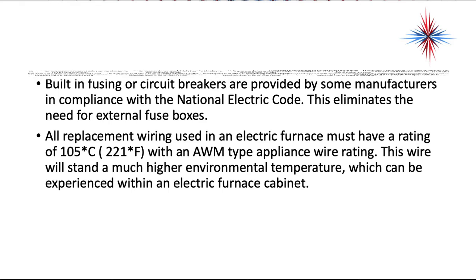Built-in fusing or circuit breakers are provided by some manufacturers in compliance with the National Electrical Code. This eliminates the need for external fuse boxes. All replacement wiring used in an electric furnace must have a rating of 105 degrees Celsius. This is 221 degrees Fahrenheit with an AWM type appliance wire rating.